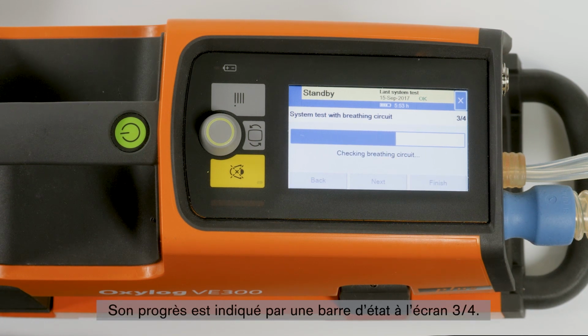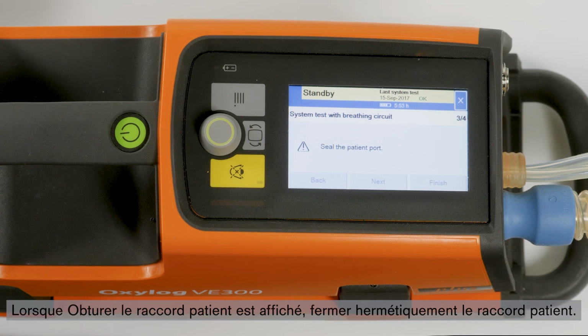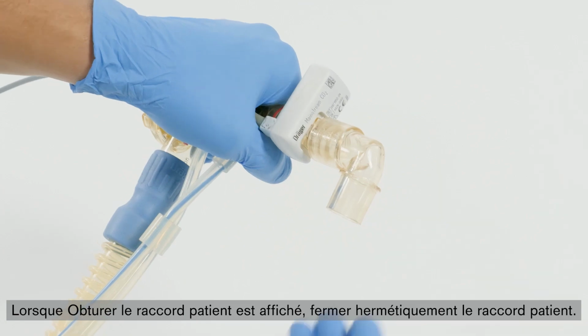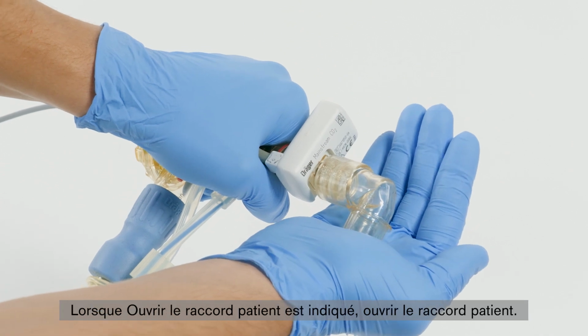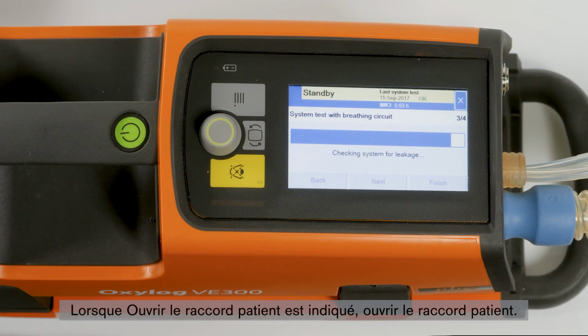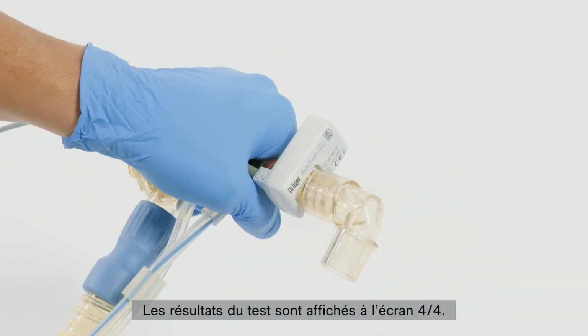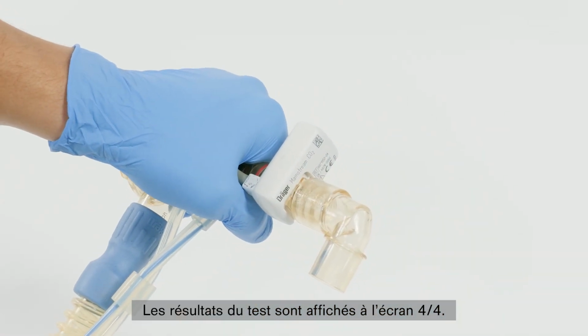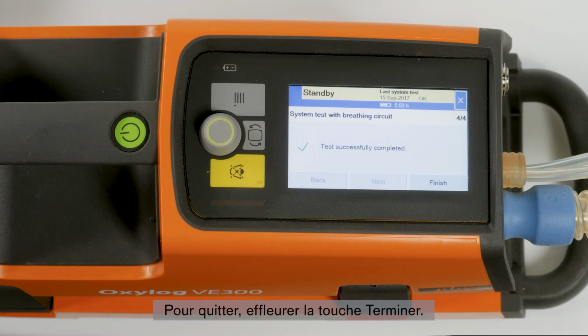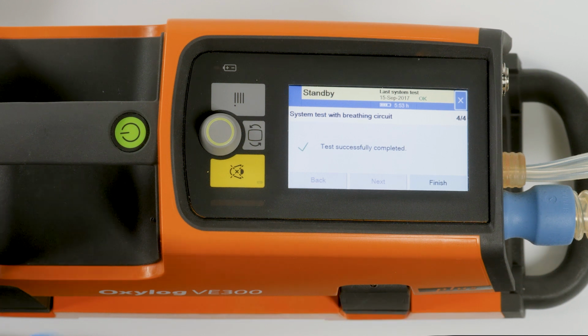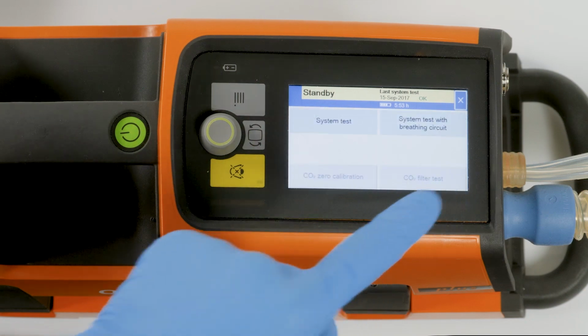The system test is then started. Its progress is indicated by a bar on screen 3 out of 4. When prompted, seal the patient port. Seal the patient port. When prompted, open the patient port. Open the patient port. The test result is displayed on screen 4 out of 4. To exit, touch the Finish button.